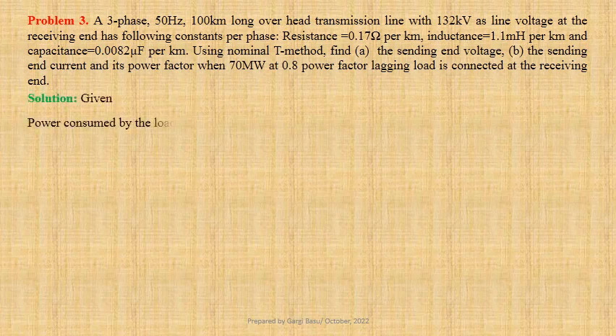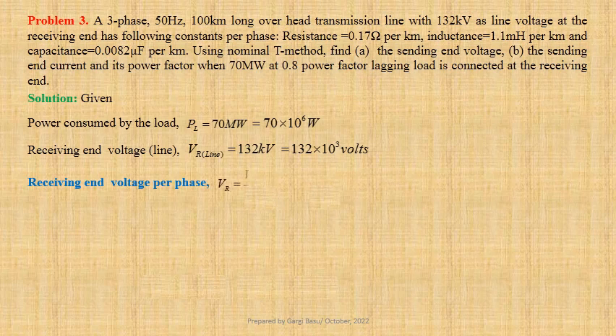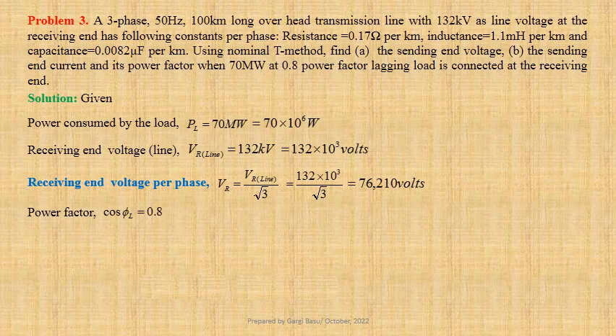Let us first write down the given data. Power consumed by the load, PL equals 70 MW, that is equal to 70 × 10⁶ watts. Line-to-line receiving end voltage, VL equals 132 kilovolts, that is equal to 132 × 10³ volts. For a star-connected system, receiving end voltage per phase, Vr equals VL divided by √3, that gives us 76,210 volts. Given load power factor, cos φL equals 0.8 lagging.